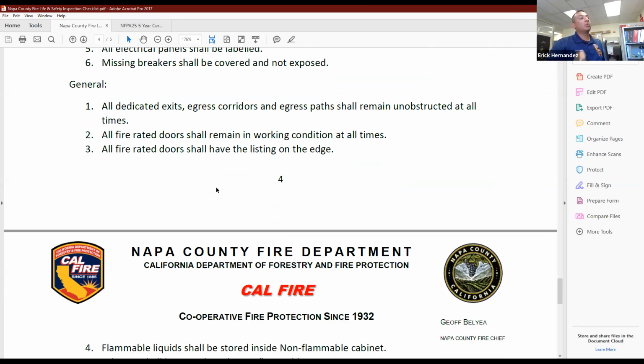Okay, and then all fire rated doors. If you have a fire rated door, then it shall be maintained. On the actual side of the door, you'll have a plate that tells you what the requirements are for that particular door. Lots of times I'm finding that people are either removing these or someone is painting over these plates. So if you are going to paint, make sure that the painter or whoever is performing the work either covers them or removes them. And once the work is performed, they put the actual plate back so that during an inspection, we can make sure that all the components that are detailed for that particular door are on there.